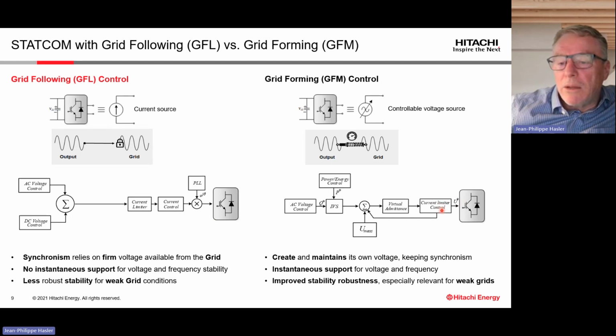The only part we keep from the GFL is the current limiter. And the current limiter will be only activated for an extremely short time. That means exactly when we have a transient, it is to limit the valve current, to protect the valve current. After the valve current has been limited to a certain value, we go back to the power or energy control to adapt the power reference such that the current in the STATCOM is again below the valve current, and we still keep all the time the behavior of this virtual impedance.